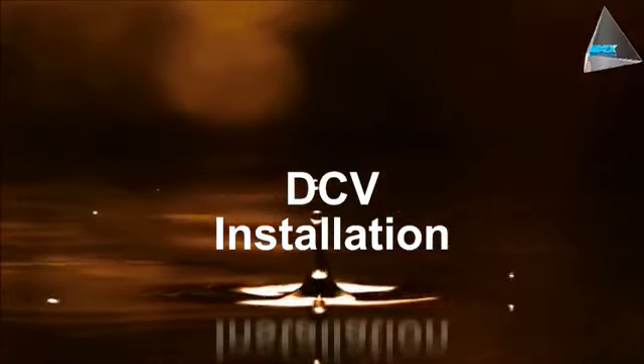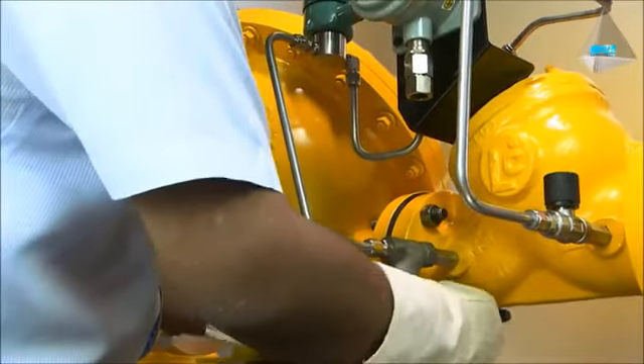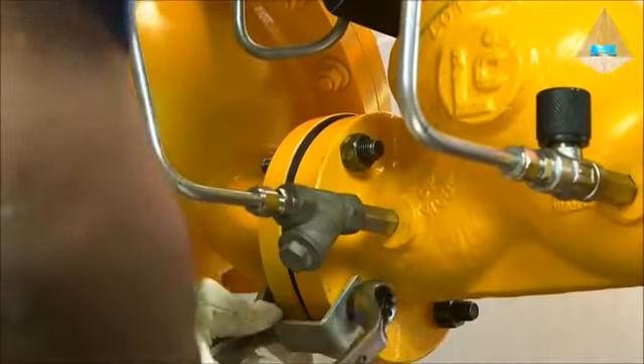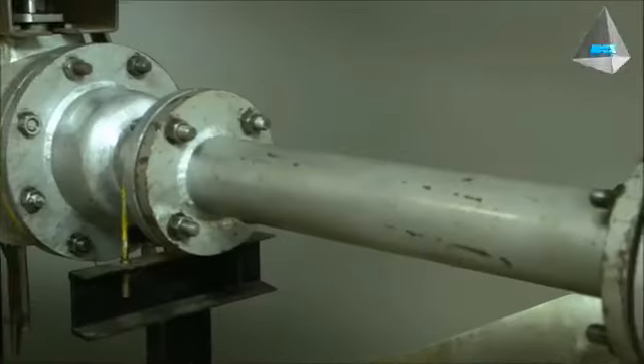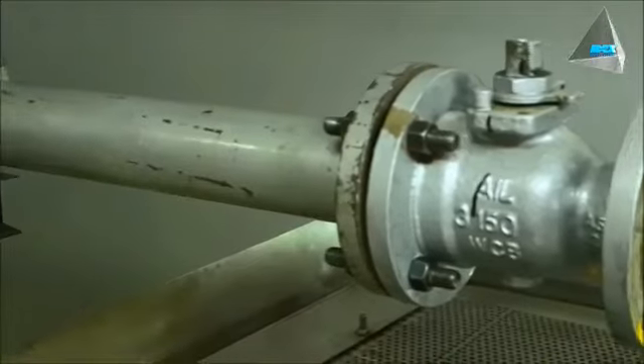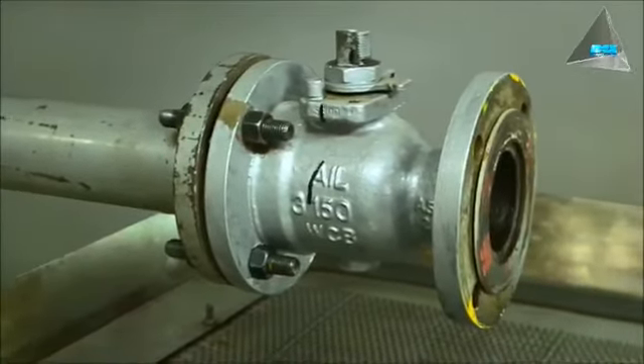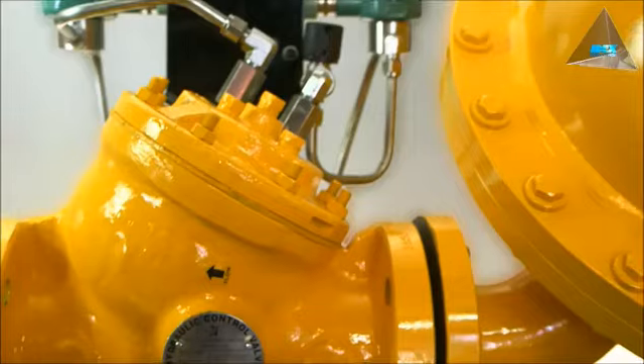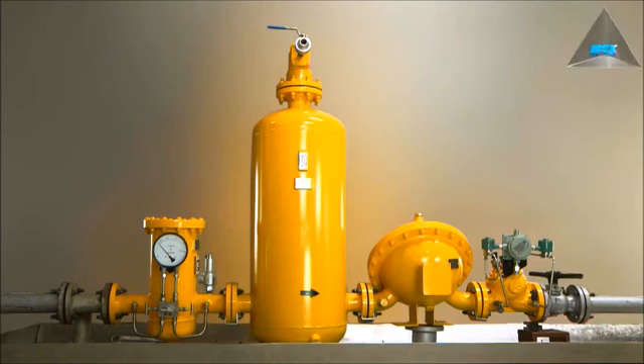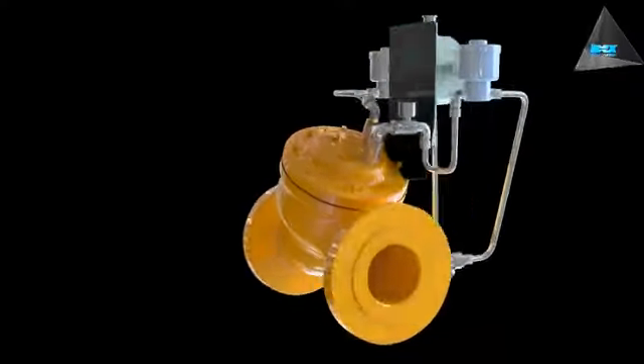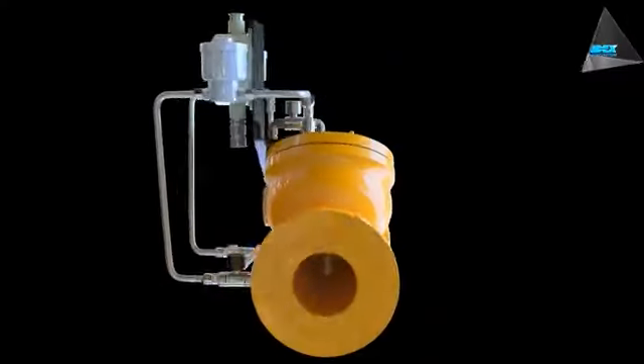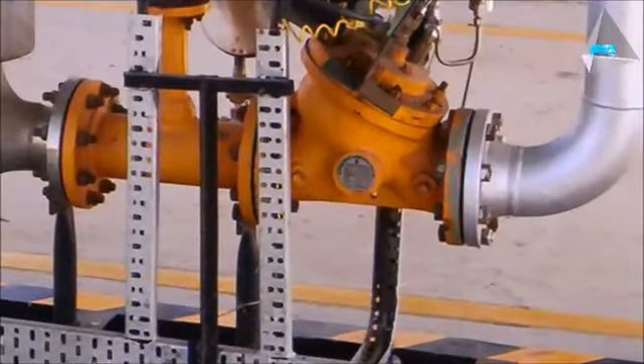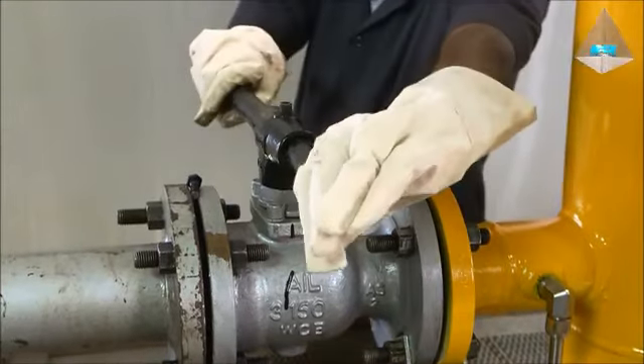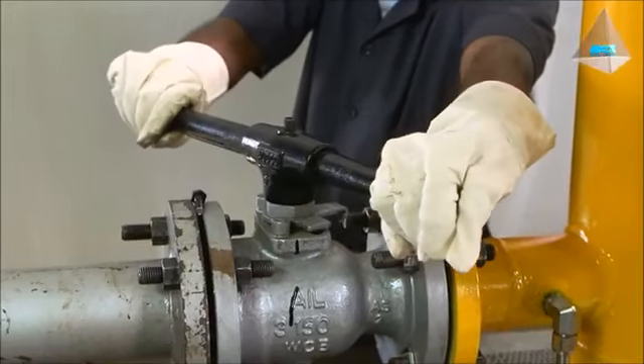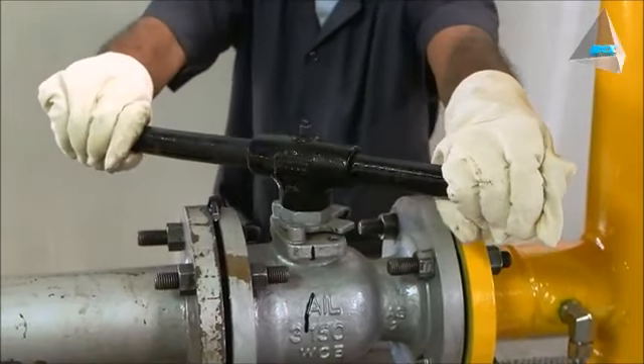DCV installation. The valve can be mounted horizontally or vertically. Space must be available for providing maintenance. Flush the pipeline. Ensure that the flushing is done with liquid compatible to the valve. Check the flow arrow on the valve body. All valves for petroleum services must be installed over the seat flow. This will help the valve to close in the event of any fail-safe condition. The valve should be adequately supported on the piping. It is recommended to install a manual valve upstream or downstream for easy draining of liquid during maintenance.